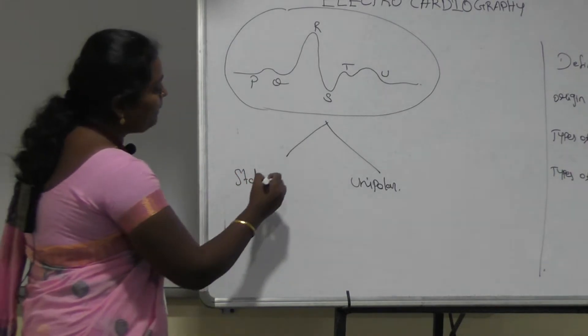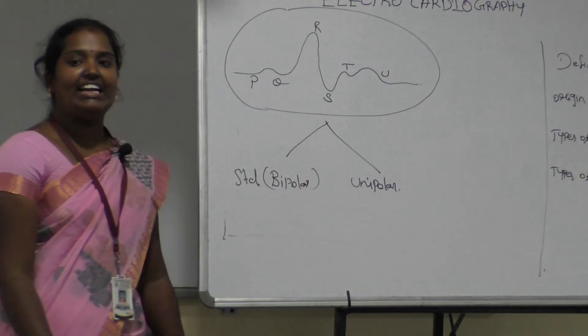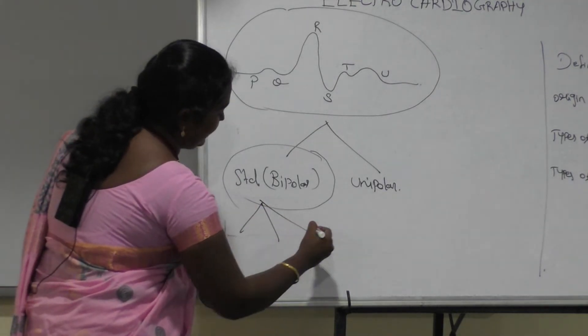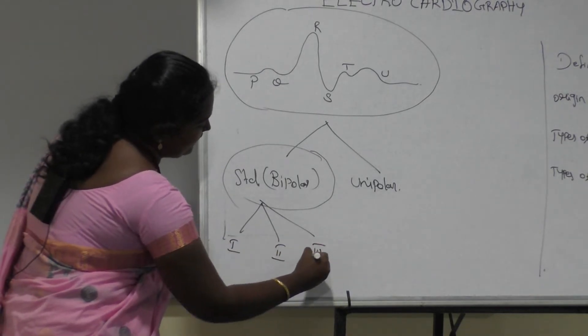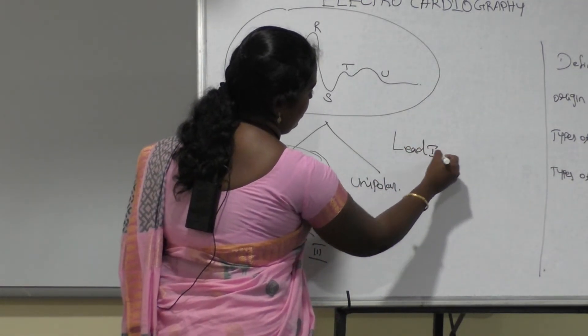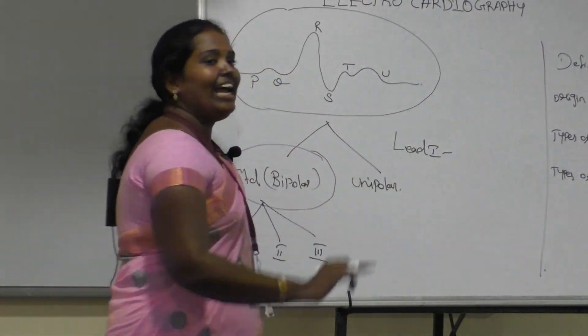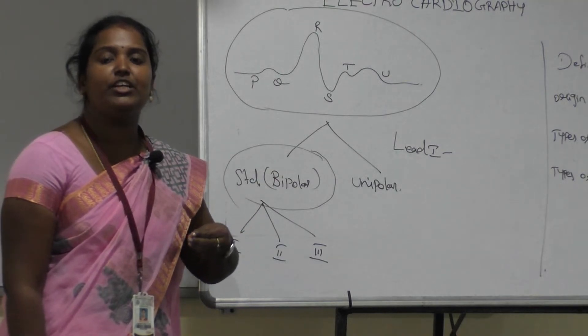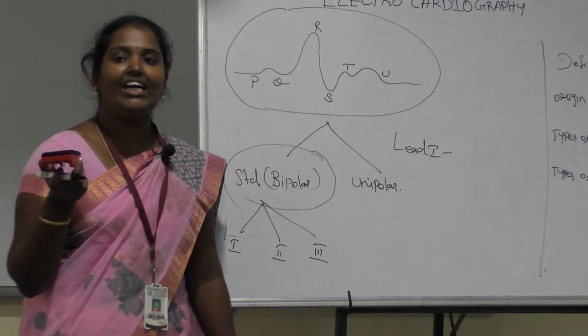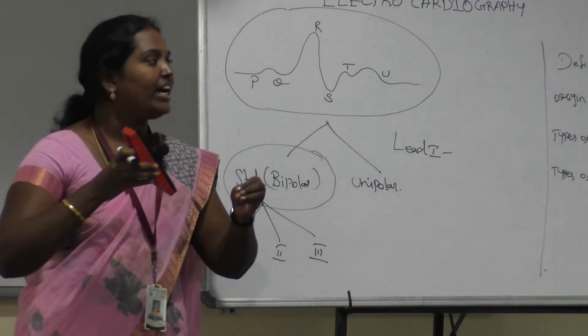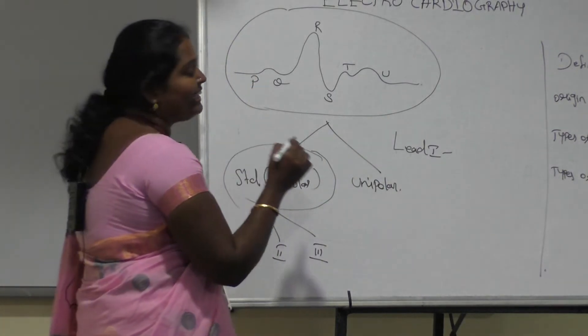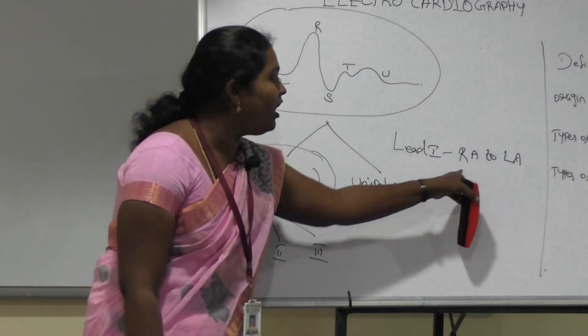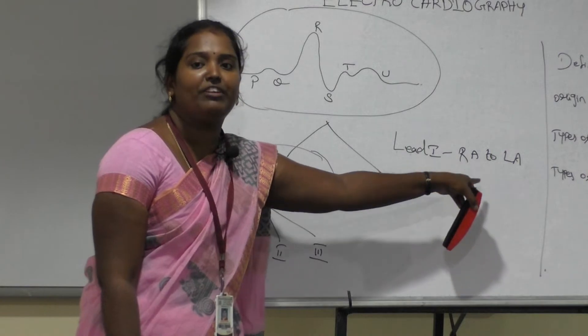The standard lead system is also called the bipolar lead system. We will now discuss only the standard lead system. It is classified into three types: Lead 1, Lead 2, and Lead 3. During the ECG process, different electrodes are placed on the human body — right arm, left arm, and left leg — with the right leg serving as the reference or ground point. For Lead 1, the electrode potential is measured between the right arm and the left arm.